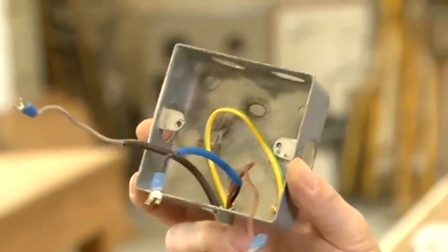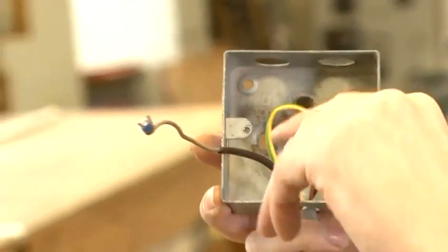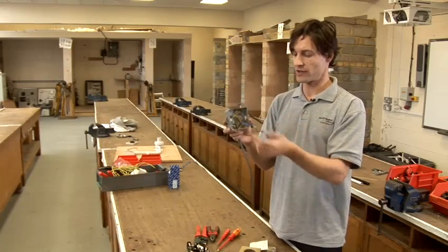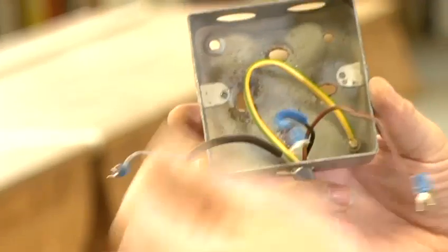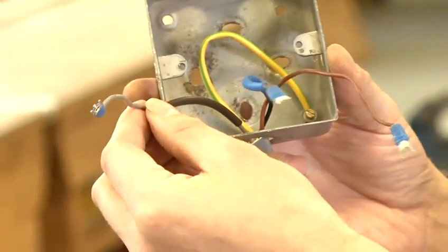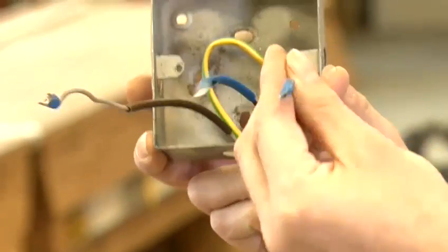It shouldn't really be wired in flex as it is part of the fixed wiring for a domestic property. I've also oversleeved each core to denote their polarity because we have a switch line, a neutral and we have a permanent live.